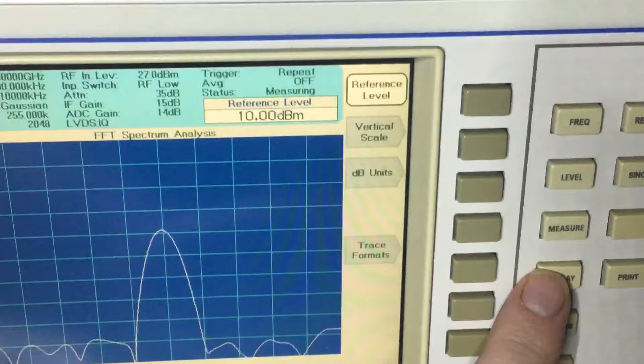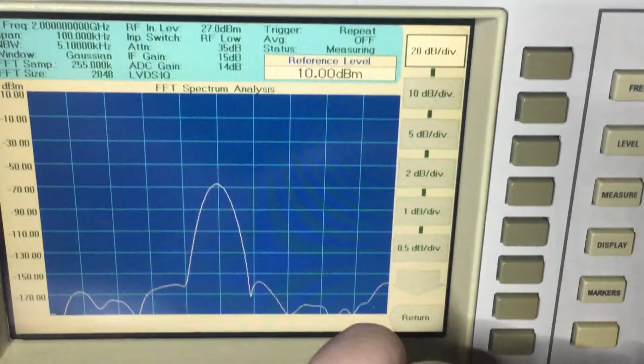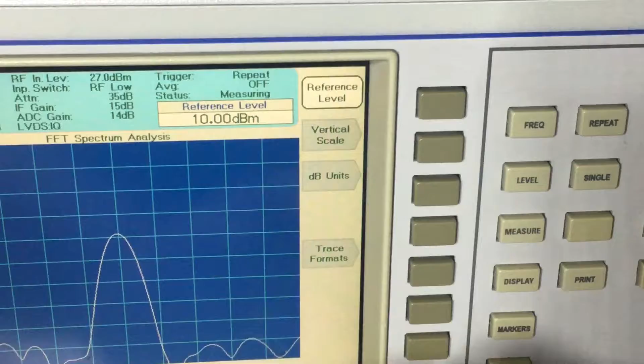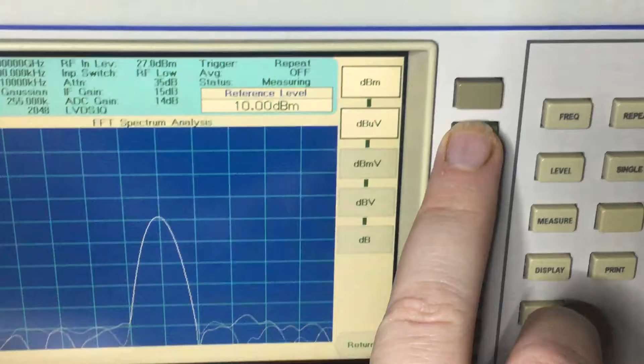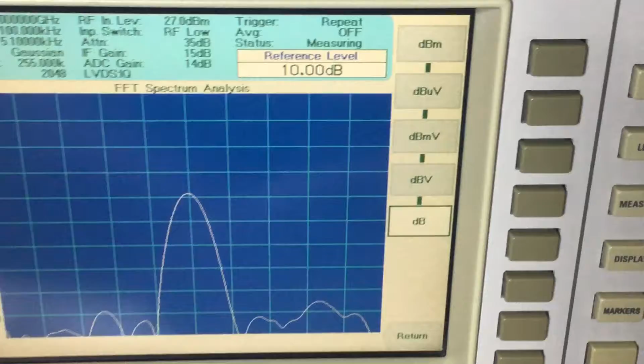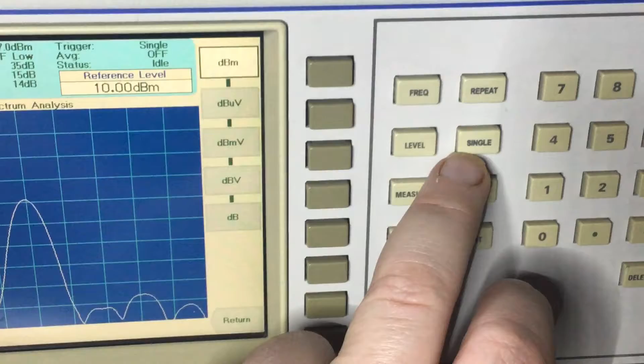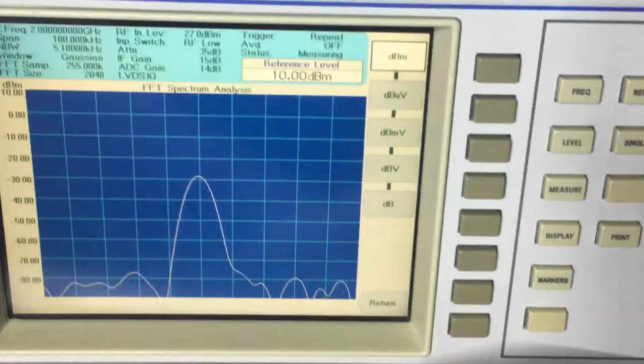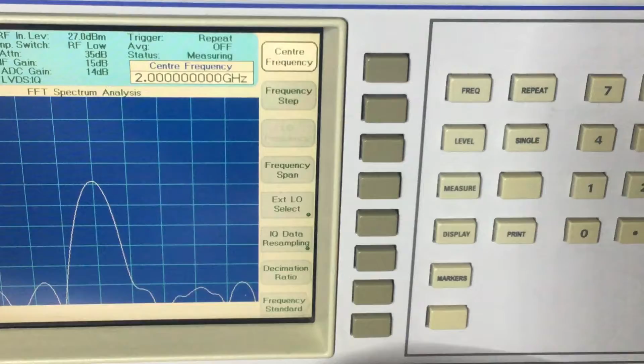Don't know what's under display. Vertical scale, so you can change that to your different limits. Obviously it's normally set to 10 dB, or you can have it at 20 dB. And then dB units as well: dBm, dB microvolts, dB millivolts, dB volts and dB, so I'll leave it at dBm. You've got a print facility as well. You can do a single, so basically if you press that button there, it'll do a single sweep. If you press it on repeat, then it'll go back to doing that. And so much you can do with it. Let me put that frequency span back to 1 megahertz, so quite a useful instrument.